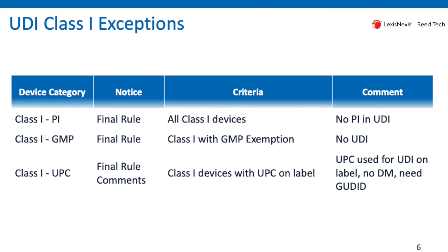The other very broad exception is that all Class 1 devices only need to have the device identifier portion — the production identifier is not required to be in the UDI. And in the event you distribute your product in a retail environment and make use of a UPC on your particular label, then that UPC identifier can be used as the device identifier and serve as the UDI. No direct marking is required for those particular devices in retail, but you still do need to make a report to the FDA's GUDID database.